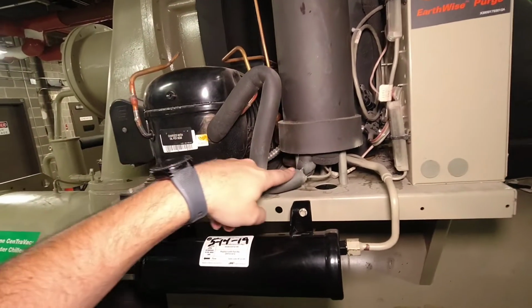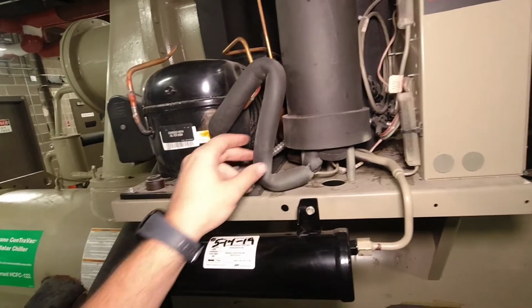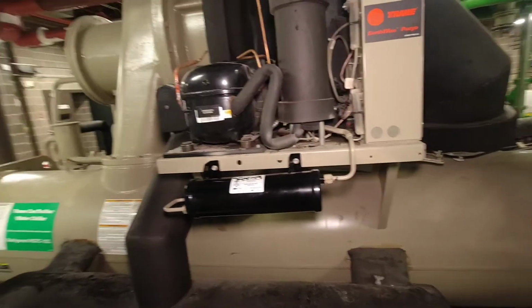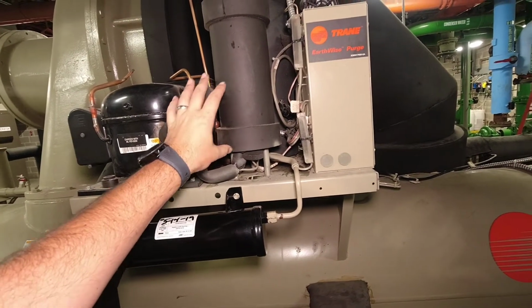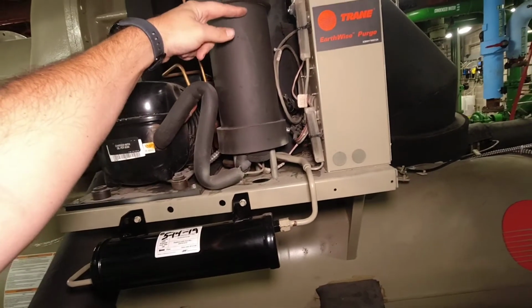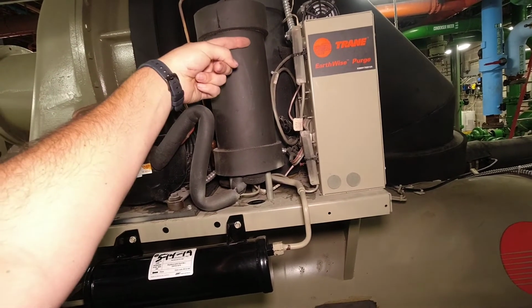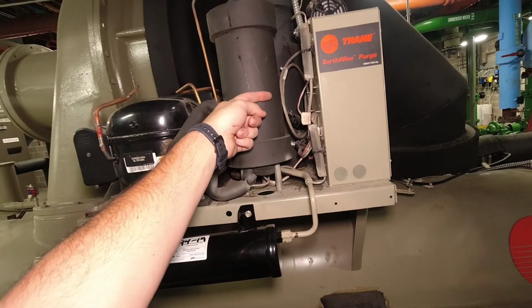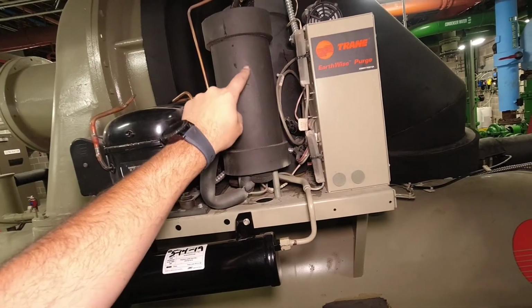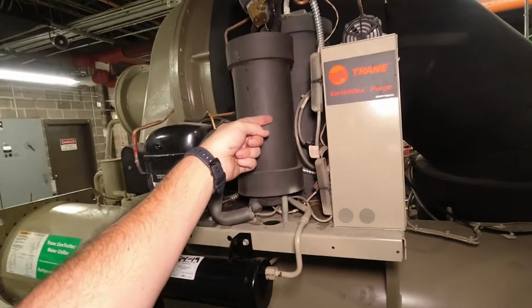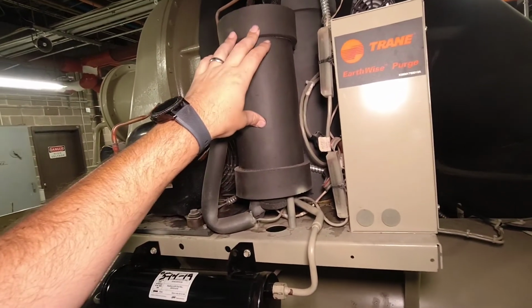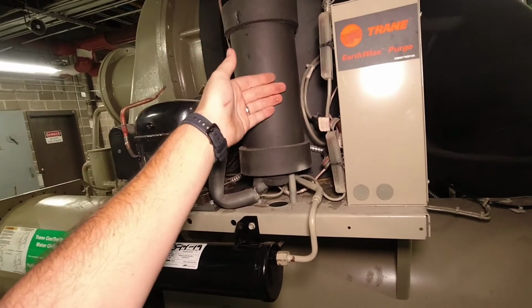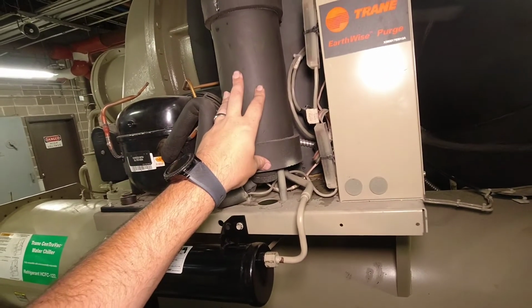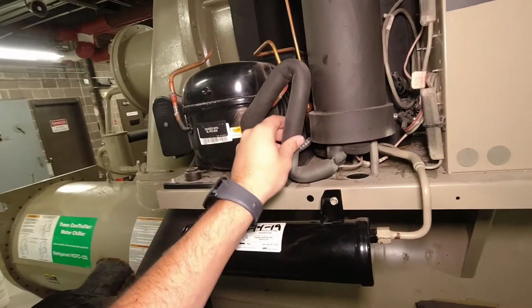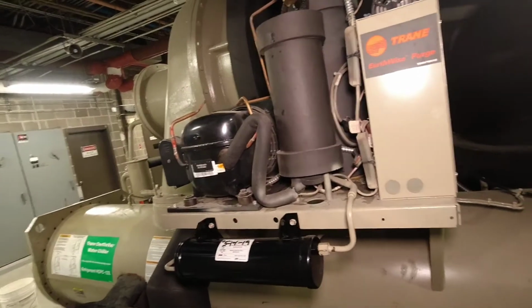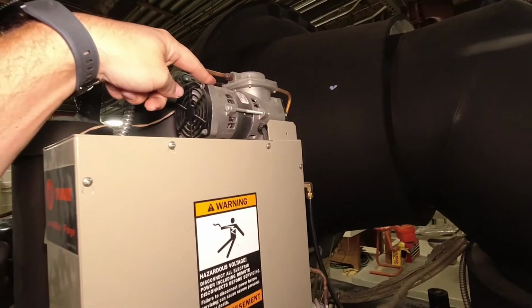So what happens though is we're monitoring this suction temp, and when we lose superheat completely and we get down to say 18, 23 degrees or below, typically, you'll see our purge go into a pump out. What's happening is the atmosphere is collecting up here at the top of the tank, and as it increases how much atmosphere is inside the tank, we lose how much load is on that coil, because as long as there's refrigerant in there, there's load on the coil. When the refrigerant level is down really low because the top of it is full of atmosphere that's getting trapped, then we don't have much load on the coil, meaning there's a lot of atmosphere and not enough refrigerant condensing, and that's going to give us a really low superheat, which in turn tells us, okay, we need to go ahead and do a pump out, at which point our pump out pump turns on.